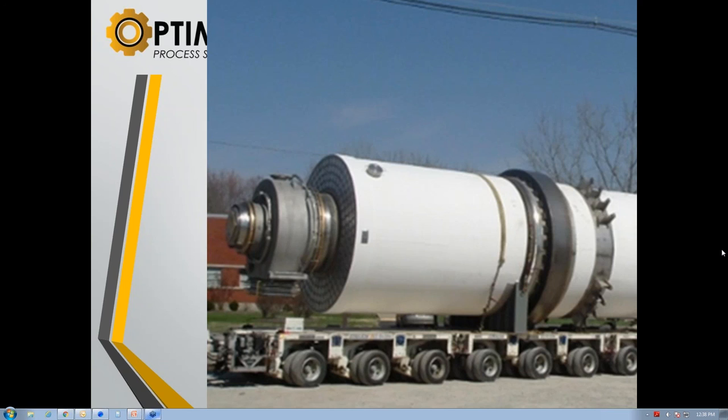Related to the steam tubes, what's the main heat transfer mode? Well, the heat transfer mode for a steam tube dryer is both conductive and radiant. We're not bringing hot air into that unit. We're bringing steam, and that's a rotating tube and shell heat exchanger. Each panel we showed on that front end represents a tube that runs from one end of that dryer to the other, typically 4-inch OD or 4.5-inch OD. They are part of the ASME vessel, and we're bringing steam in there, say 150-pound steam that's going to be at 367 degrees, with a latent heat of about 860 BTUs.